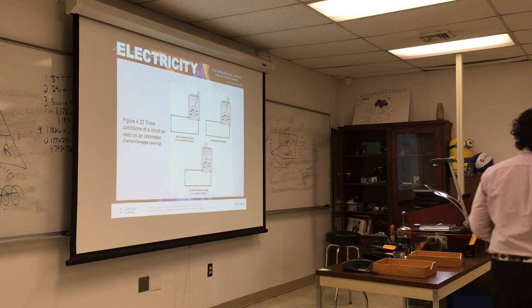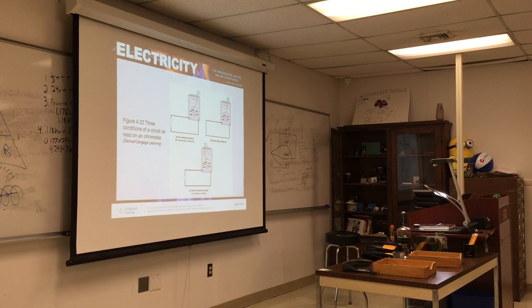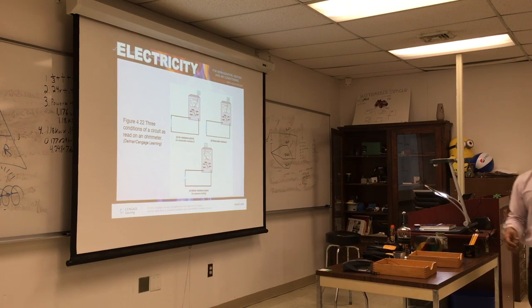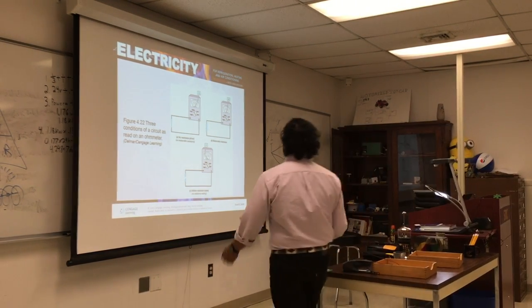So what you do is you wrap the coil - let me show you quickly. I want to clamp the multimeter, so I'll wrap it 1, 2, whatever you need, 3 times, and whatever reading I get, you divide by 3, because you're reading 3 times the magnet. So that's one trick to do if the amperage is very small - you can wrap it around.